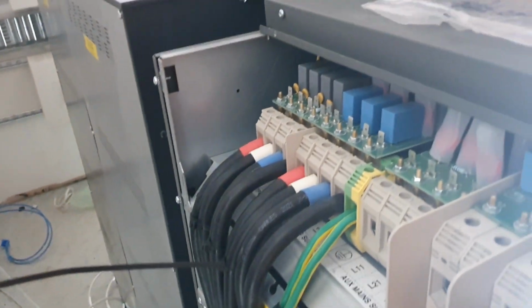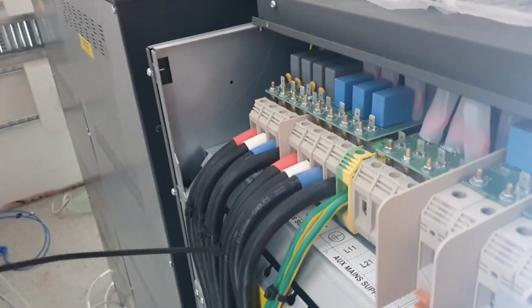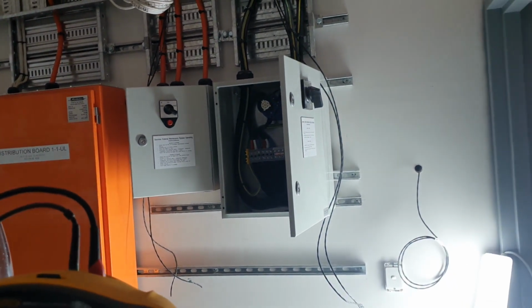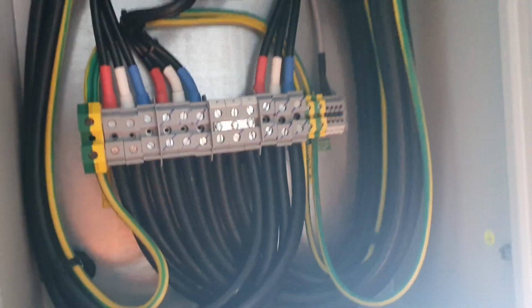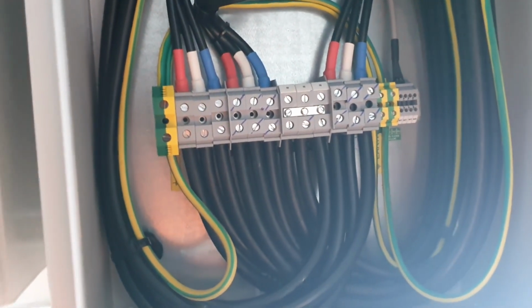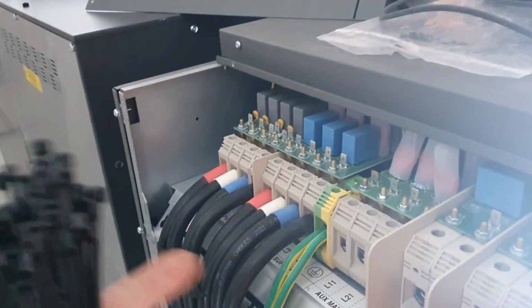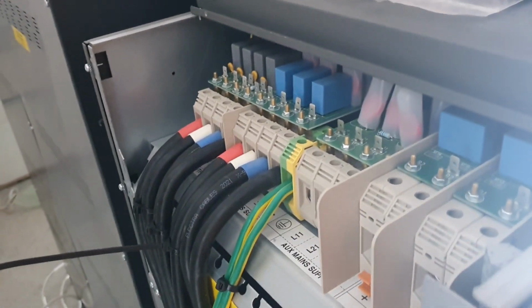I need to change the phase rotation. I'm gonna do it back in the main board because doing it here is a bit difficult. If I do it back there, all that wiring is fine, but this here is fucking impossible to change, so I'm not touching that. I'm just gonna reverse the polarity, one of the phases back to the boards, because this needs clockwise rotation. I don't know why it needs clockwise, but it needs clockwise.